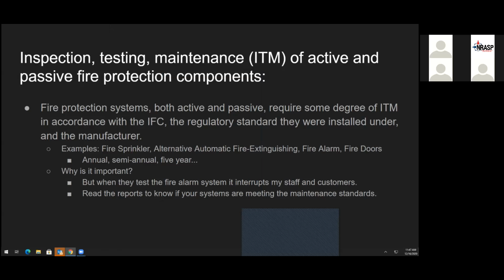From my experience, when I come and look at those reports, sometimes a violation might be noted on an inspection, testing, and maintenance report, and the person that I'm walking through the facility doesn't even know that there was a violation. So it's very important that you have someone in your facility that's taking that responsibility and reading thoroughly through those reports as they come in, because you need to make sure that your system's being inspected, tested, and maintained properly, because if you need it, you want to know it's going to work.